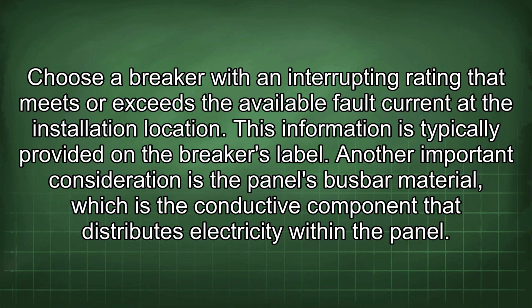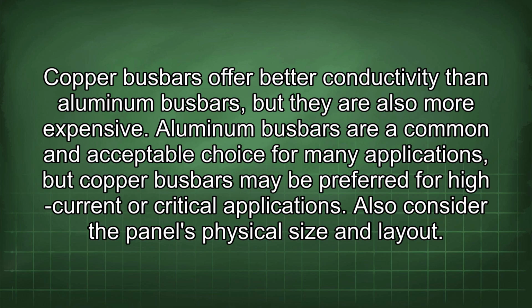Another important consideration is the panel's busbar material, which is the conductive component that distributes electricity within the panel. Copper busbars offer better conductivity than aluminum busbars, but they are also more expensive. Aluminum busbars are a common and acceptable choice for many applications, but copper busbars may be preferred for high current or critical applications. Also consider the panel's physical size and layout.